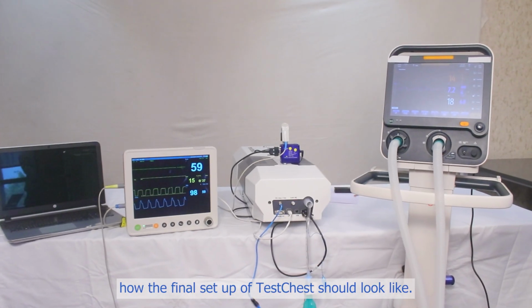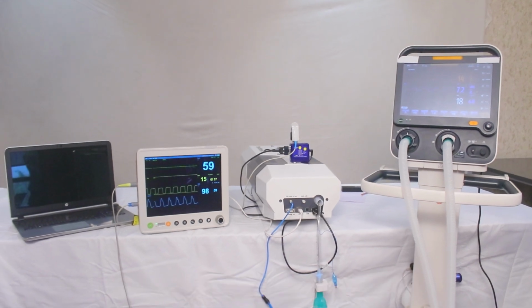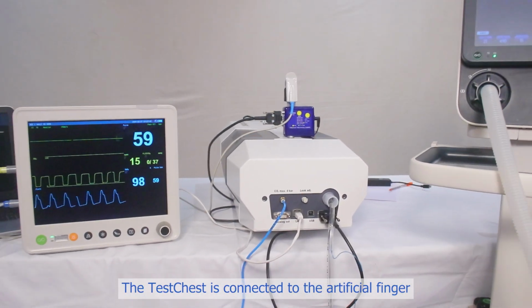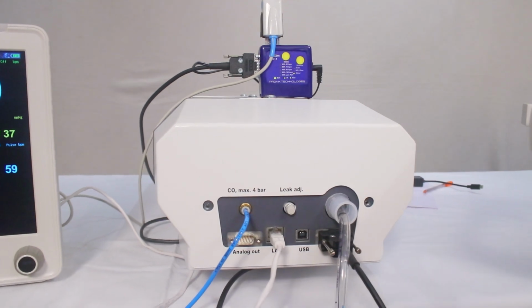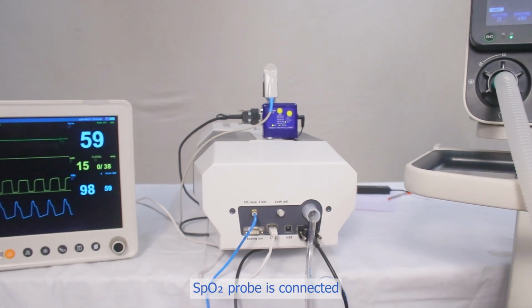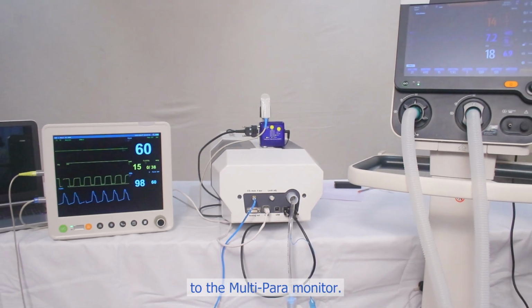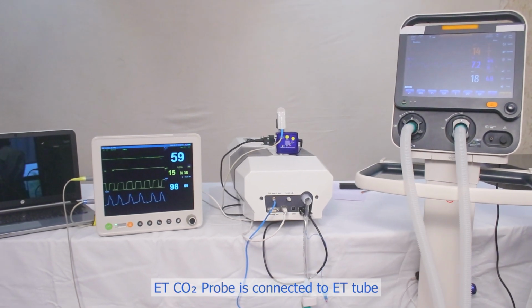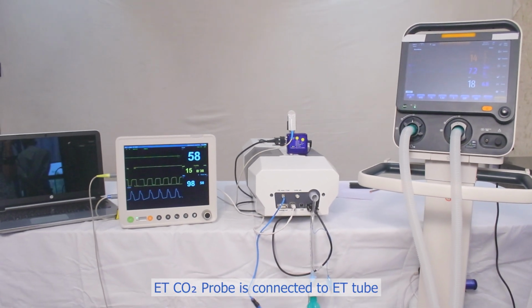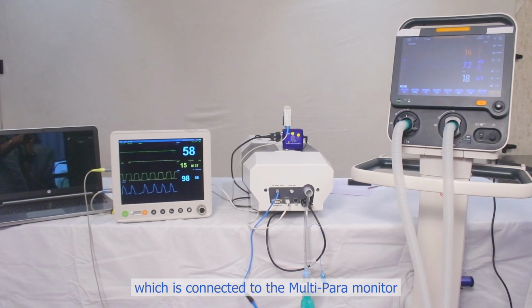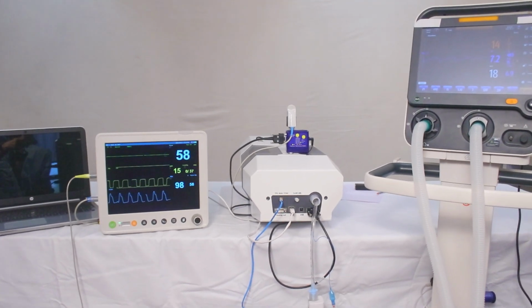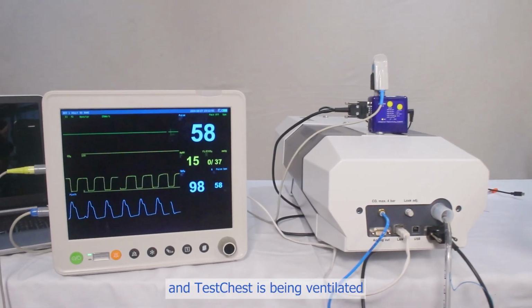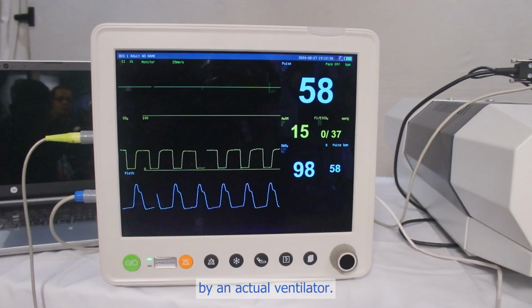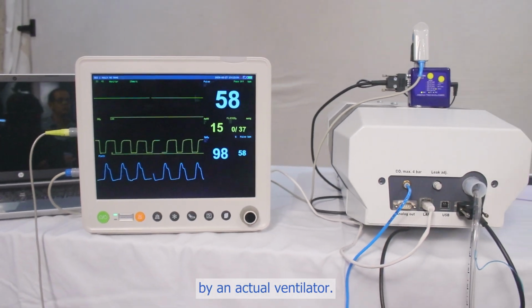This is how the final setup of TestChest should look. The TestChest is connected to the artificial finger. SpO2 probe is connected to the multi-para monitor. EtCO2 probe is connected to the ET tube, which is connected to the multi-para monitor. And TestChest is being ventilated by an actual ventilator.